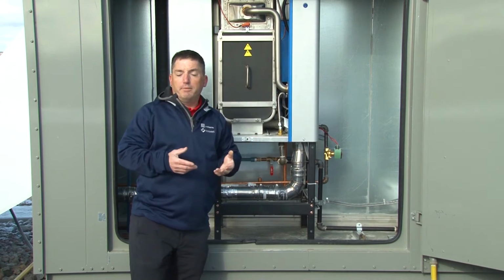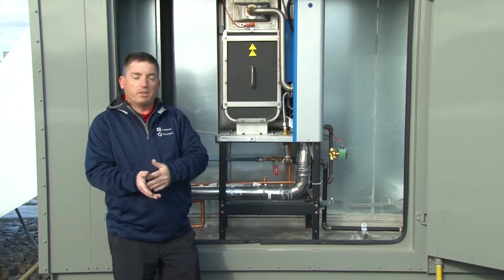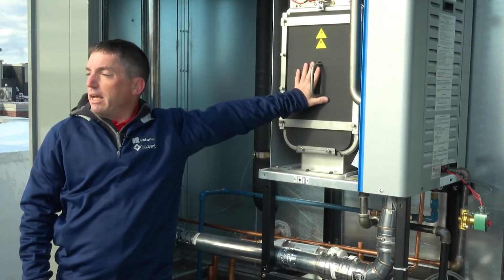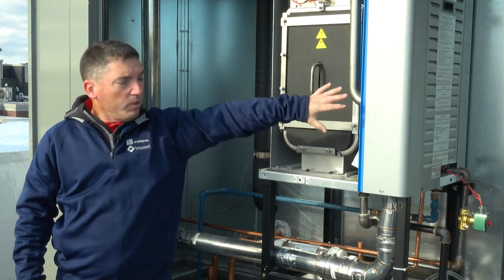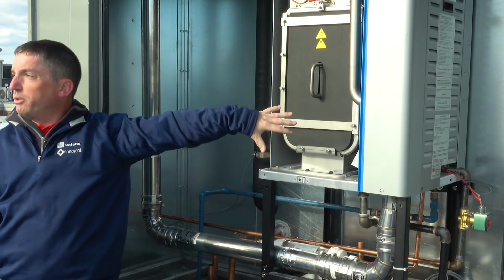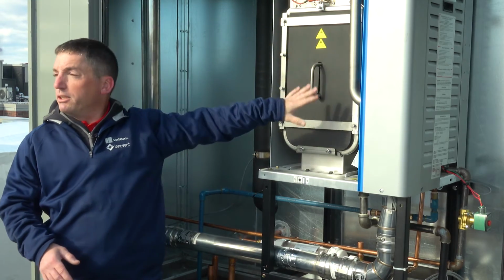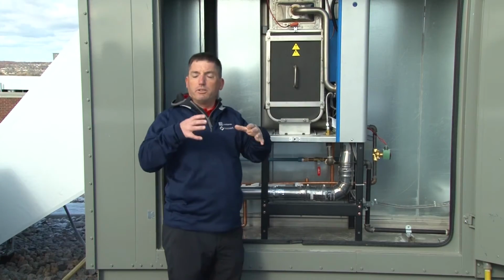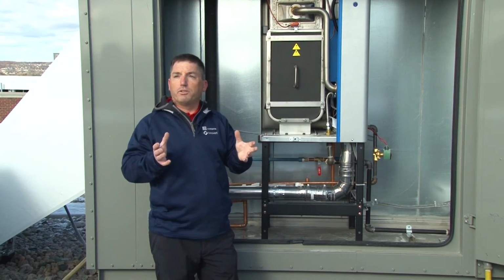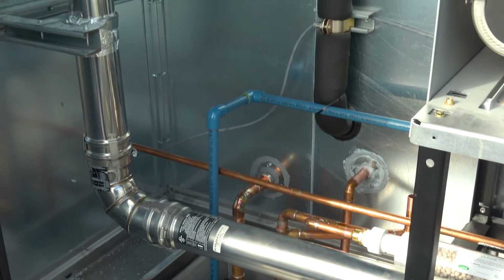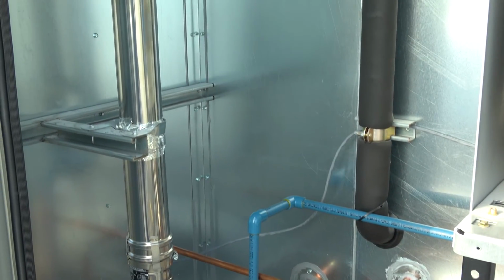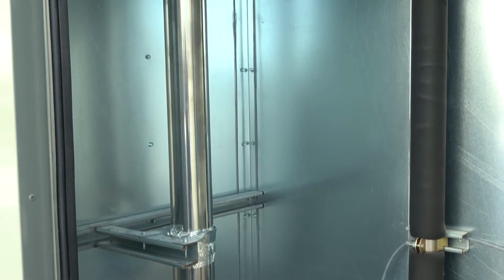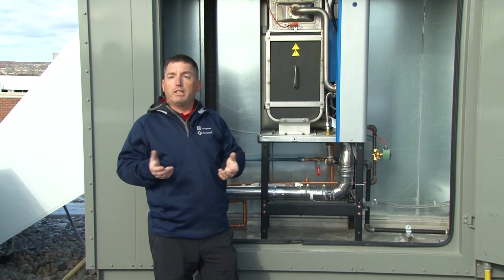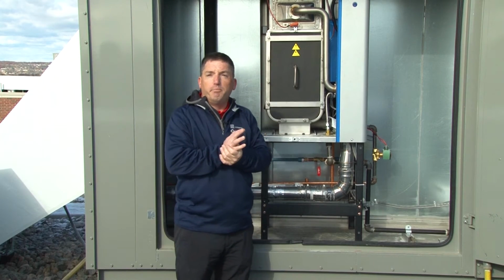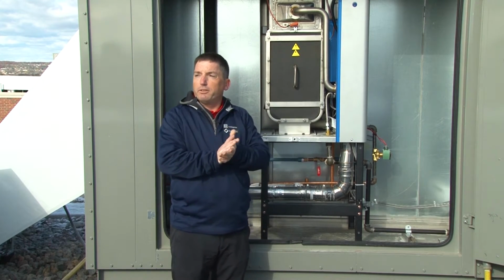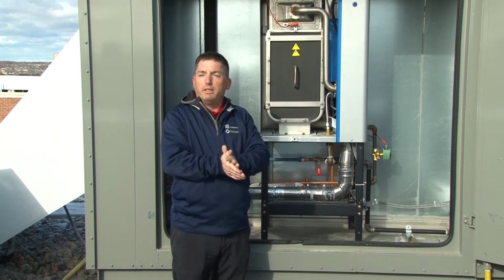They function very similar to your kettle at home. Obviously, we're filling this tank with water. We have an in-shot gas burner and a tubular heat exchanger inside that is going to heat up and cause the water to boil, boils off into steam, which then gets injected into the supply air behind me. Obviously, anytime you boil water, any minerals, debris, etc. that is in the water is going to be left behind.